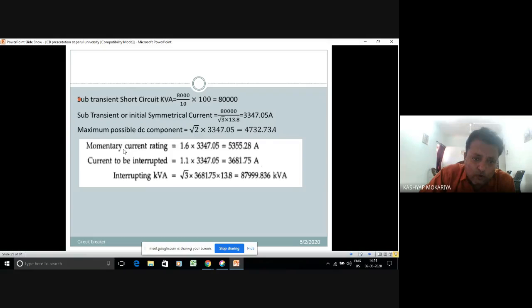So I get the momentary current rating is 1.6 into my subtransient. Why did I say momentary? Because the subtransient state of the breaker is for 2 or 3 cycles only. So 1.6 into 3347.05. So it is 5355.28 ampere.